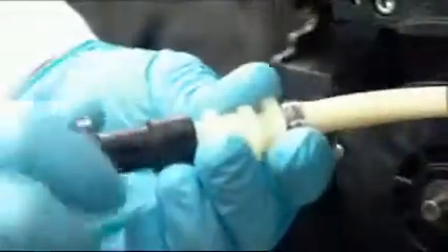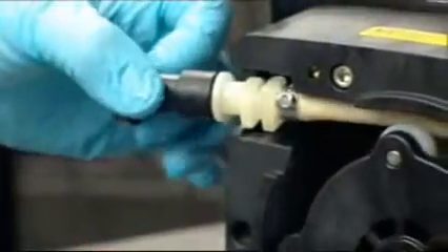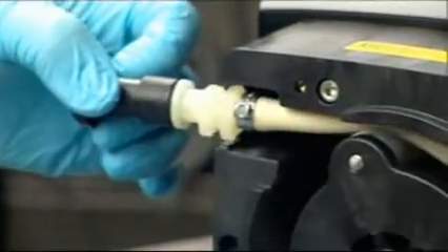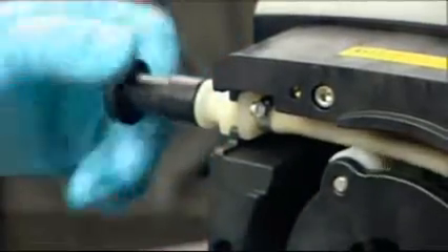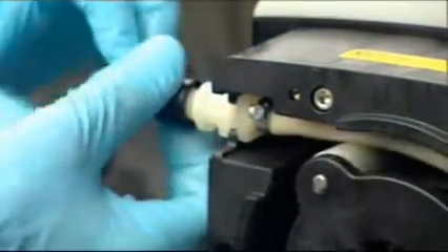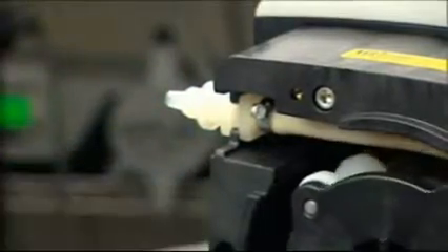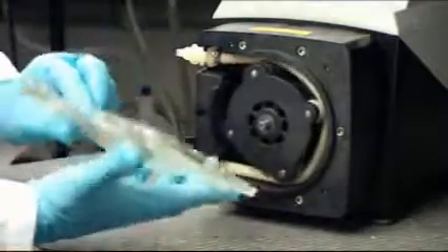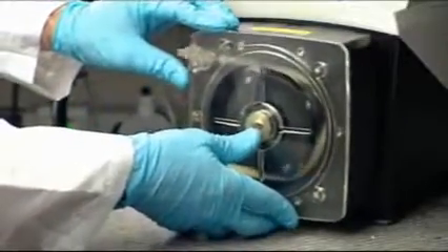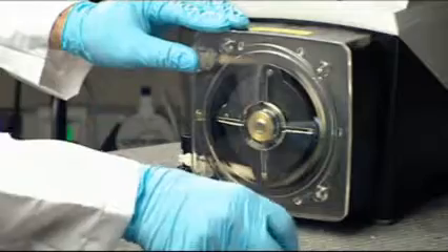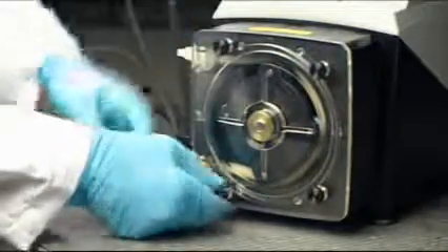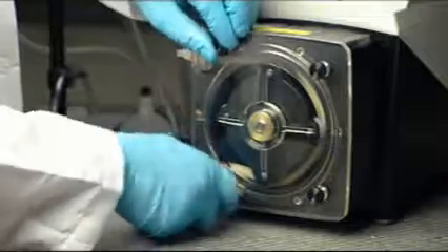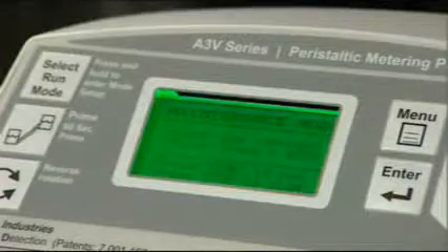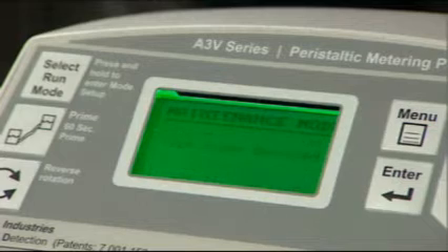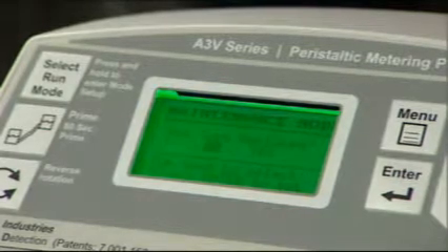An installation tool is included with the A3 pump. Install the tool on the pump tube adapter on the outlet side. Gently pull on the outlet fitting until the fitting aligns with the outlet slot. Press the fitting into the pump head. Remove the installation tool. Replace the pump head cover. Be sure that the 4 thumb screws are fully installed. The A3 will detect the pump head cover and prompt the user to reset the pump tube timer to 0.